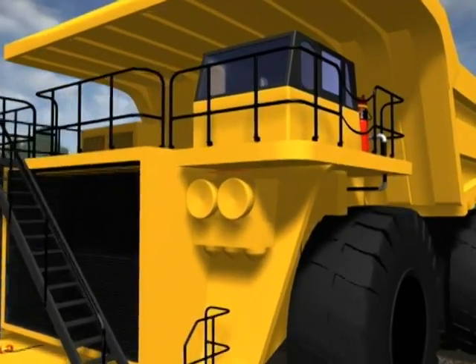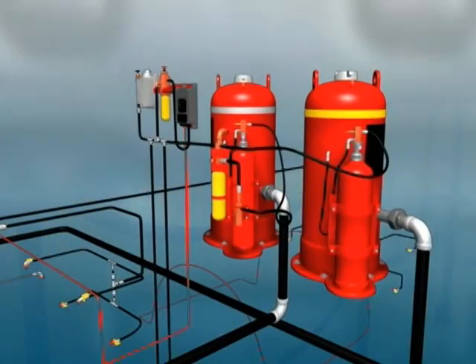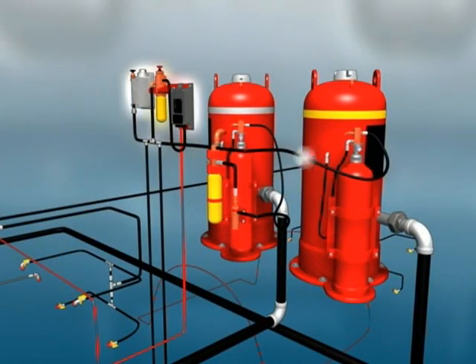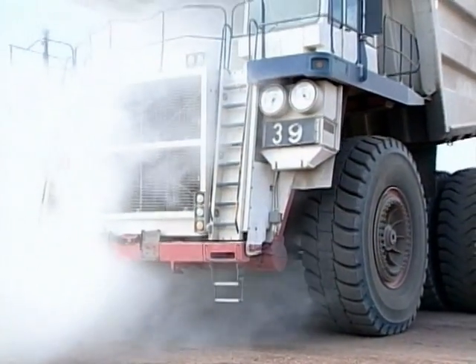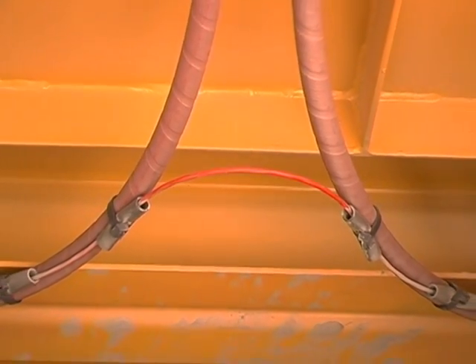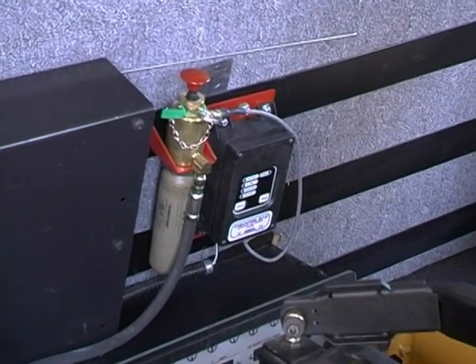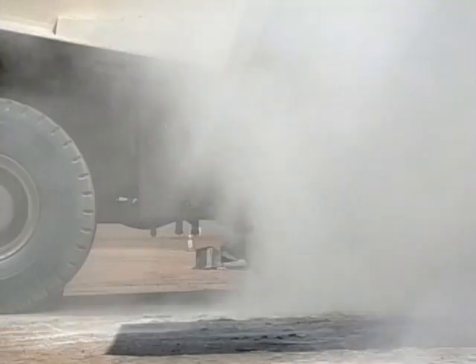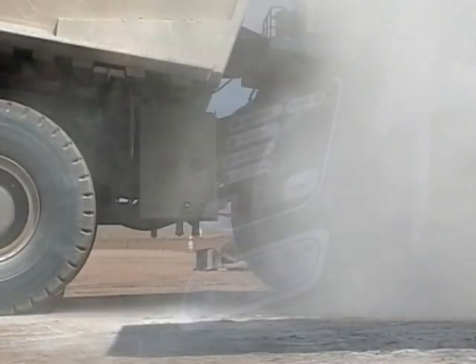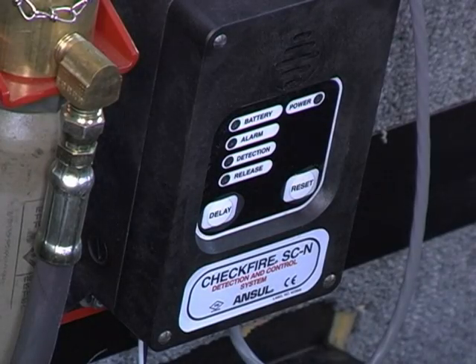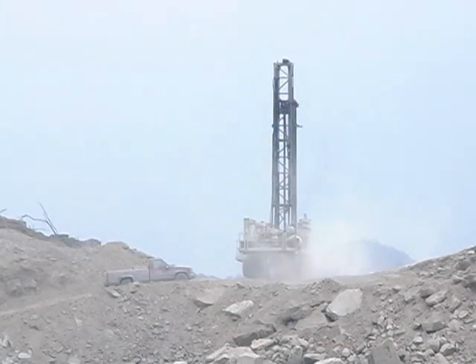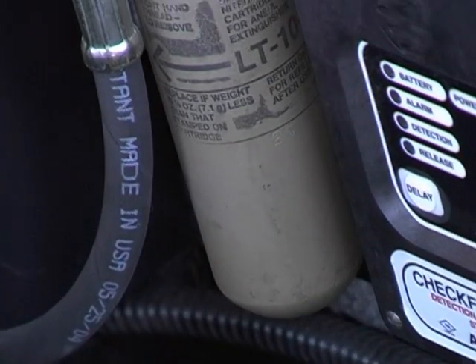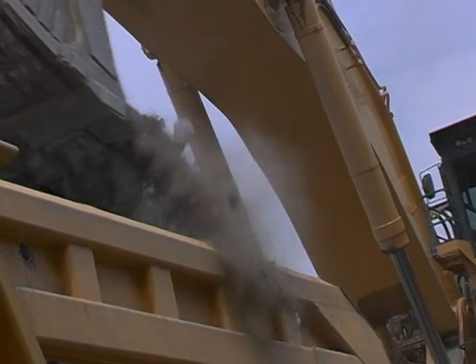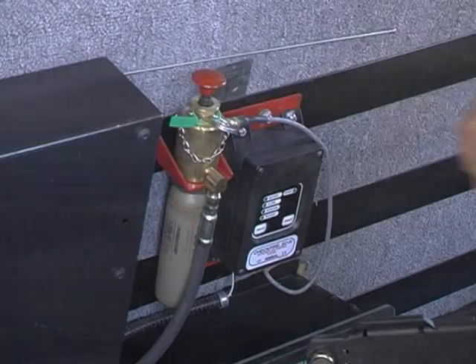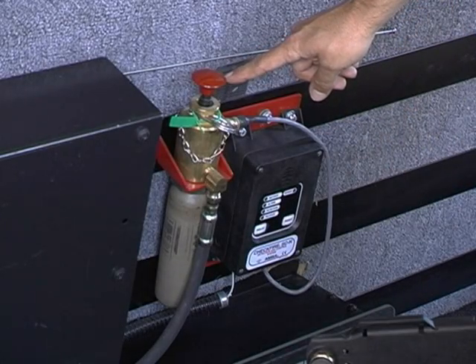The ANSUL Check Fire Detection and Control Actuation System provides rapid activation and deployment of the fire suppression system. With the thermal detection options of linear wire or spot detectors, ANSUL's Check Fire provides automatic fire detection, equipment shutdown, and fire suppression system actuation. With its environmentally sealed control module, the Check Fire system resists shocks and excessive vibration. It has self-checking diagnostics and a completely self-contained power source for the ultimate reliability in the most difficult conditions. The system is also equipped with backup manual actuation capability.